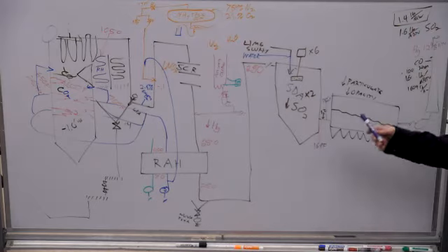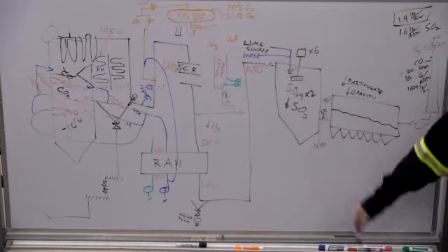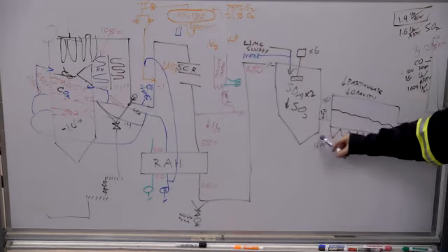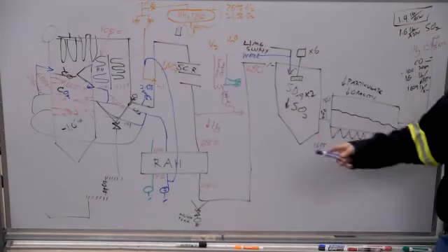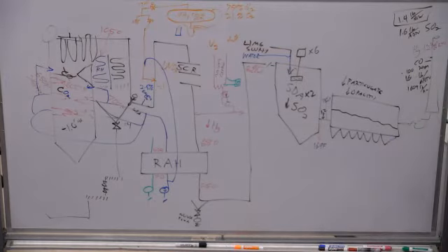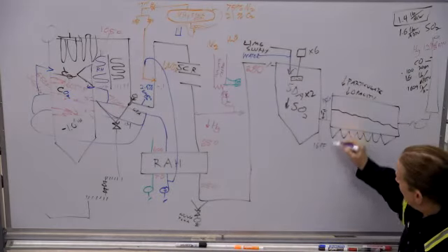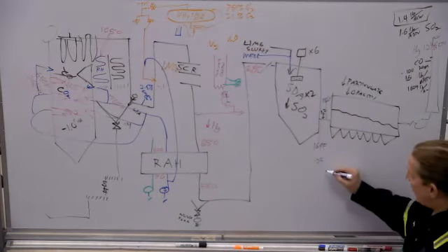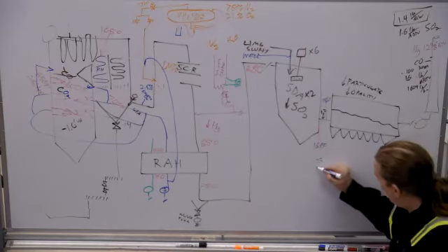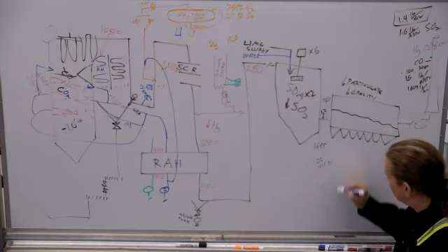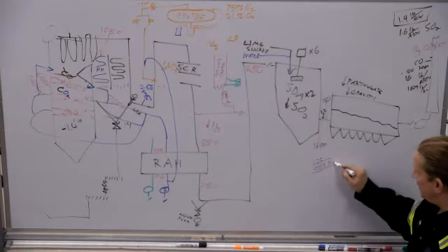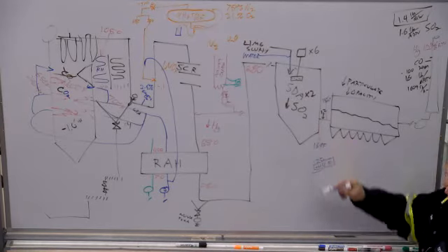So as long as it's warm enough, it's okay to have high humidity, and then it gets too cold and it's no longer okay. Similarly, when we get too cold back here, it starts to form clumps up on the side. The ash gets too clumpy and it doesn't do its job right. So we're looking at the dew point and it comes up with some number like, let me try some math, 125. And then we have a dew point approach control of 44 degrees. That's where you get your 169: whatever the actual approach set point is, combined with whatever the dew point monitor is reading, gives you that 169.